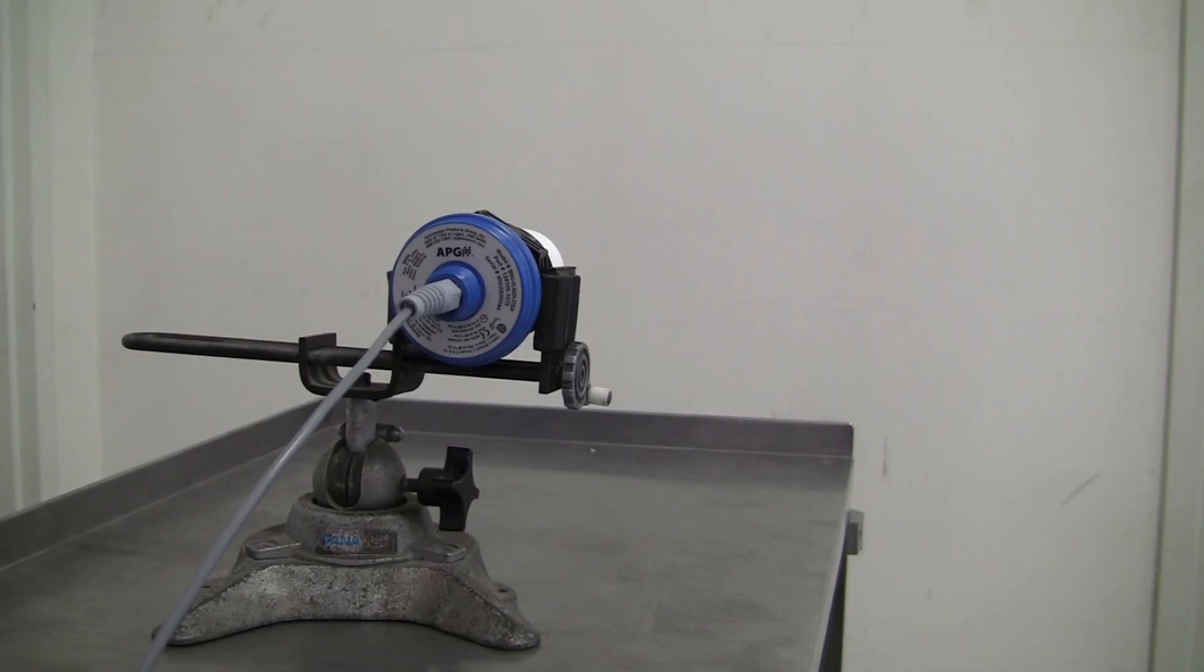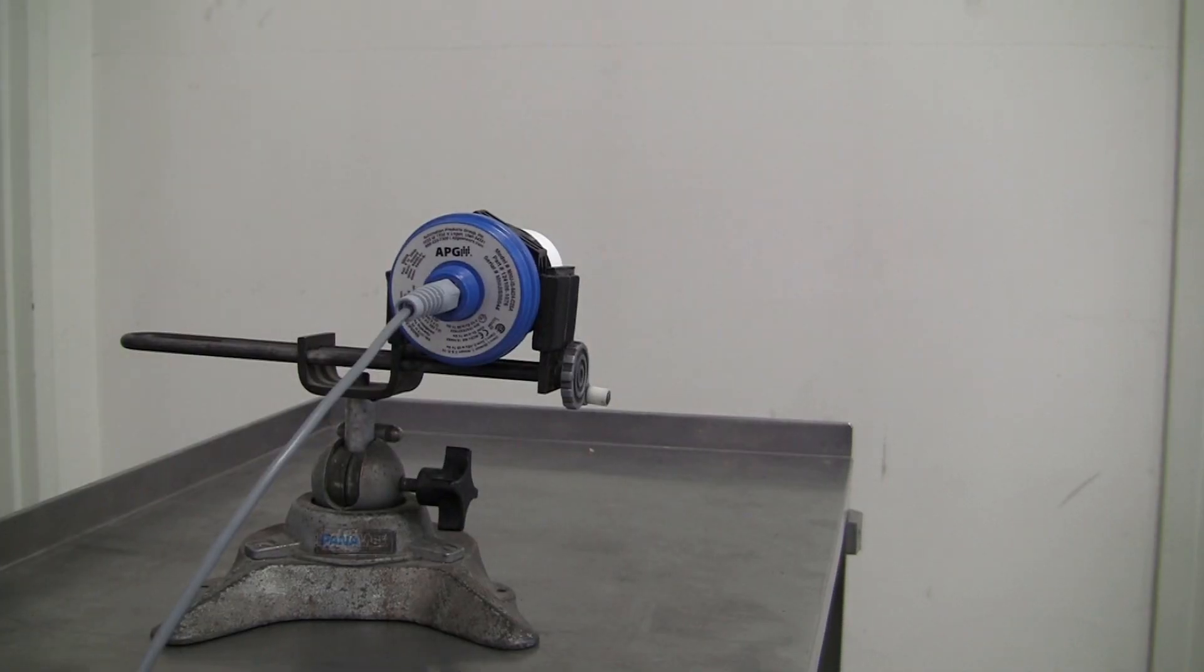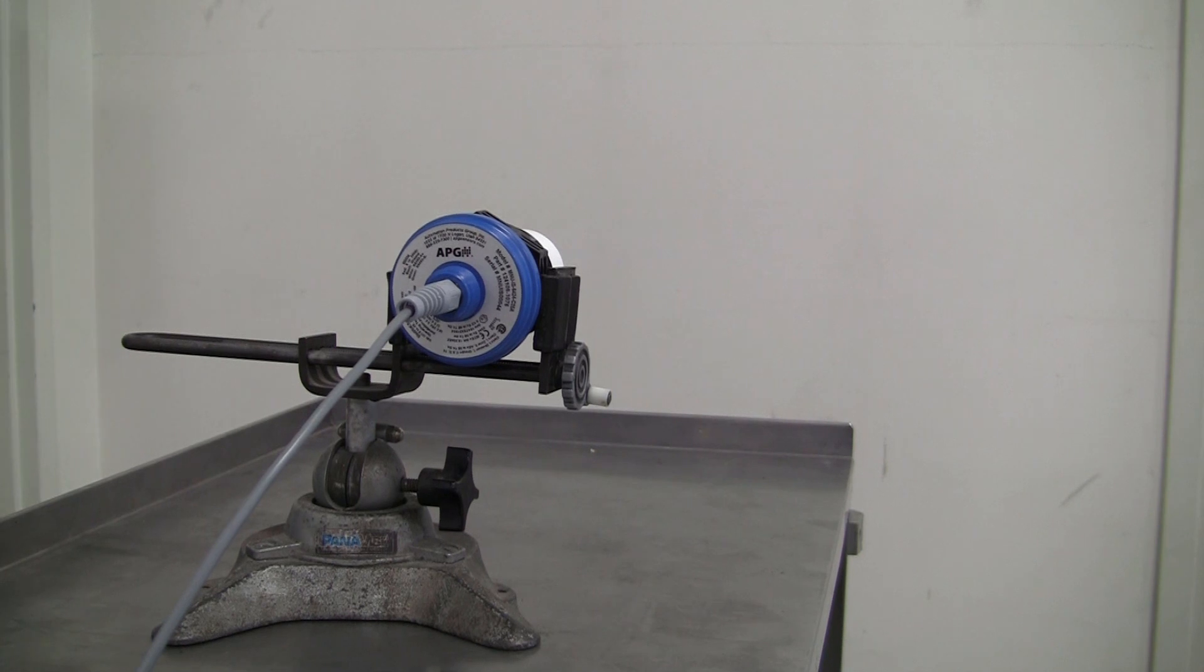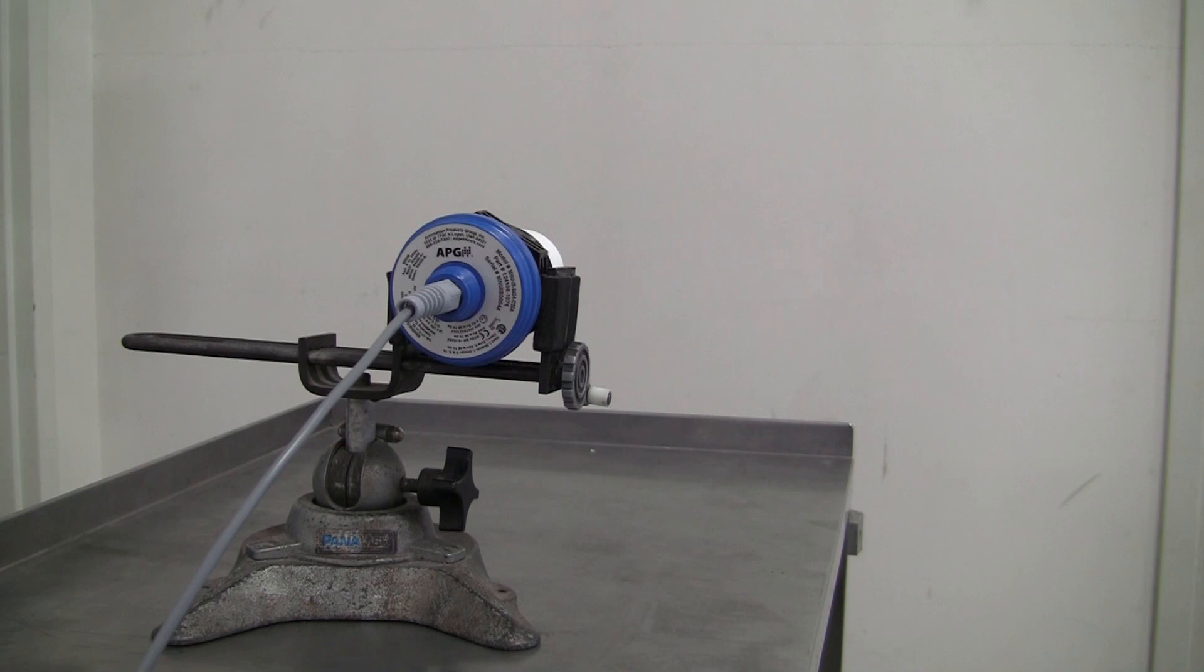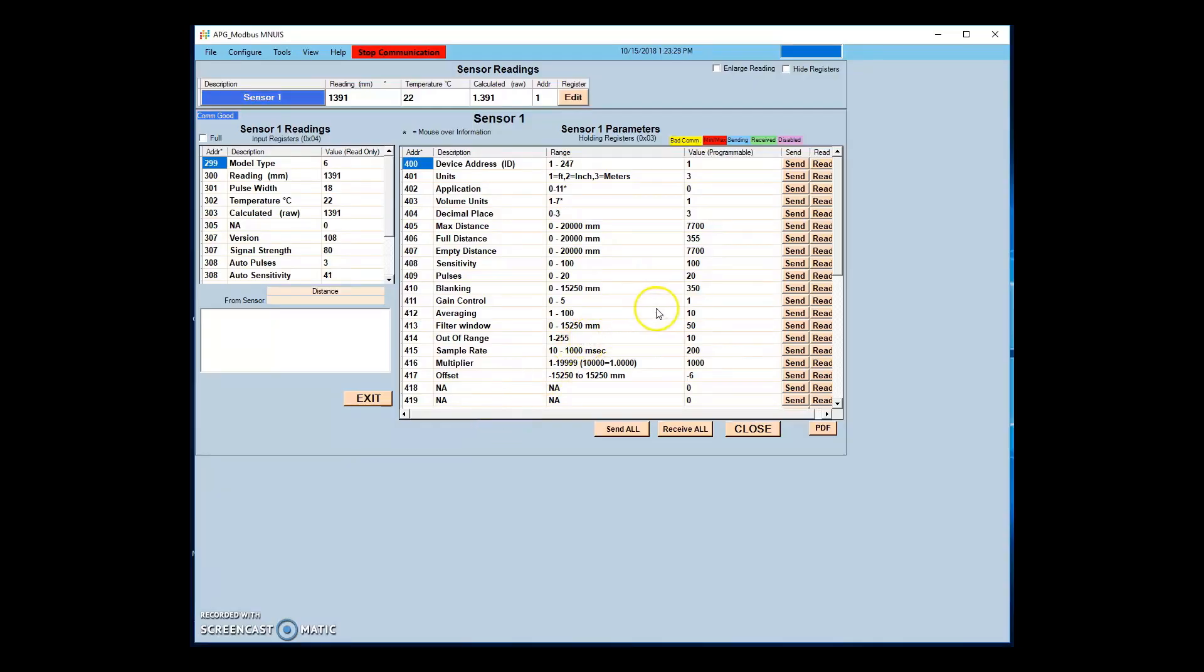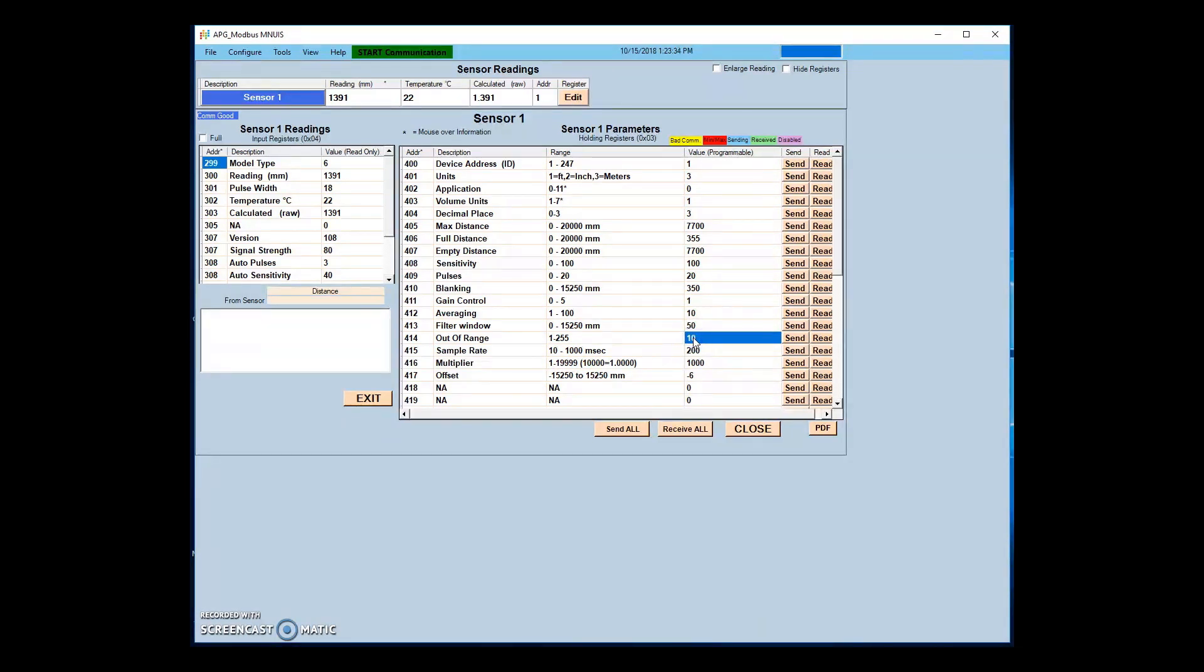Here we have a sensor set up reading around 1.4 meters. With the sensor programmed with default settings, we can see that the sensor is averaging 10 readings to determine the displayed value. The filter window is set so that any readings more than 50 millimeters different from the current reading will not be accepted into the averaging buffer, and will instead read into the out of range buffer.